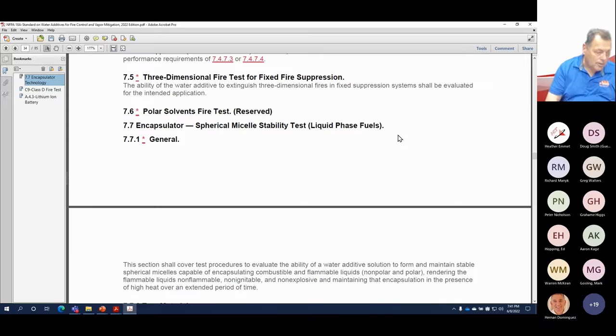So in order to control the fire in 1 minute, extinguish it in 5 minutes, and pass the burn-back resistance test, I have to have quality, stable bubbles that remain stable in the presence of high heat. That's what this test measures.